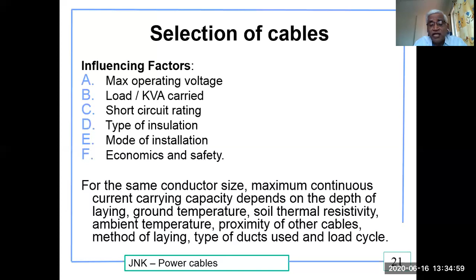For the same conductor size, maximum continuous current carrying capacity depends on the depth of laying, ground temperature, soil thermal resistivity, ambient temperature, proximity of other cables, method of laying, types of ducts used, and the load cycle.